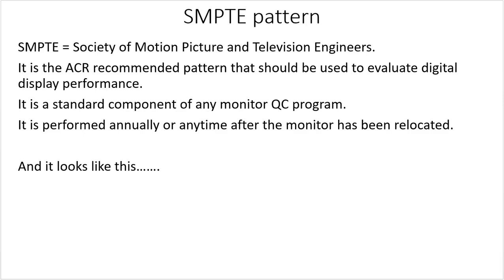SMPTE is the ACR-recommended pattern that should be used to evaluate digital display performance. It is a standard component of any monitor QC program. It's performed annually — once a year — or any time the monitor has been picked up and moved. If you move it to a different room, you have to run the SMPTE pattern.